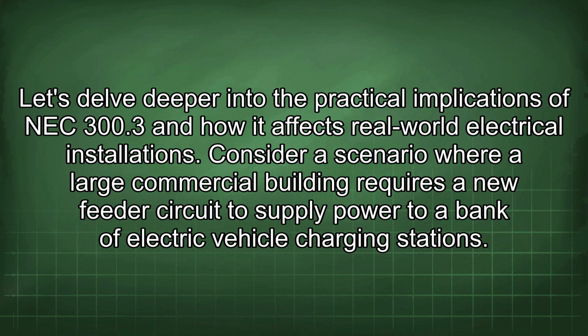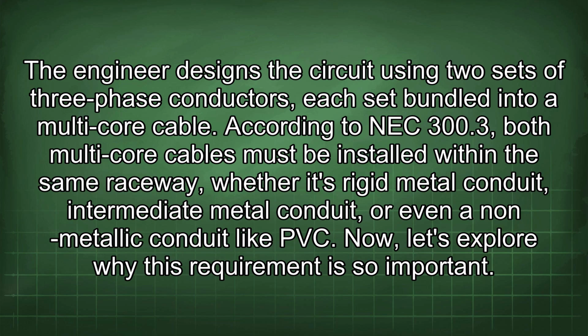Consider a scenario where a large commercial building requires a new feeder circuit to supply power to a bank of electric vehicle charging stations. The engineer designs the circuit using two sets of three-phase conductors, each set bundled into a multi-core cable. According to NEC 300.3, both multi-core cables must be installed within the same raceway, whether it's rigid metal conduit, intermediate metal conduit, or even a non-metallic conduit like PVC. Now let's explore why this requirement is so important.